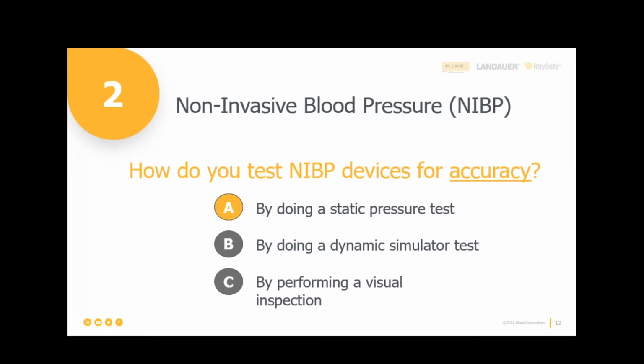Well, what can cause problems in picking that pressure? Patient movement of any kind, talking, believe it or not, okay? Shivering when a patient is recovering from anesthesia, or when they're hypothermic and beginning to warm up, they're shivering. Crossing their legs, right, exactly. All of these things change the dynamic and make it hard for the algorithm in the patient monitor to properly make the measurement and display the right pressure. Therefore, an important reason to do the repeatability test, but after you've done the accuracy. Leak test, pressure relief, accuracy, and the static pressure level comparisons.